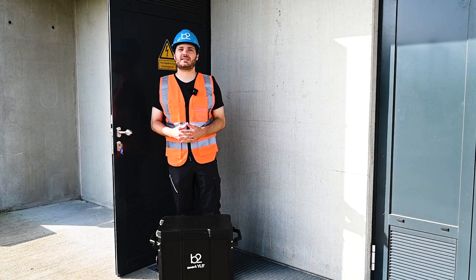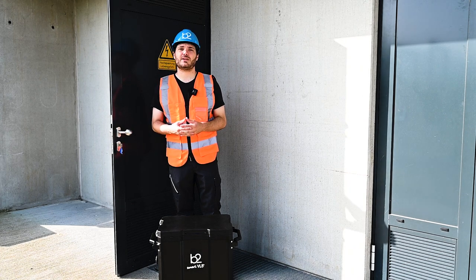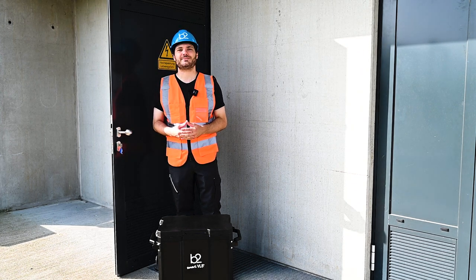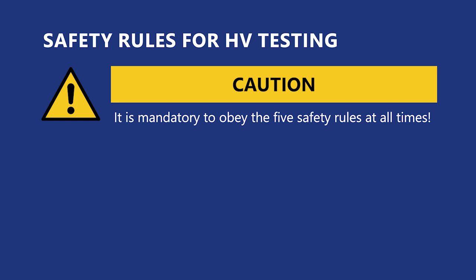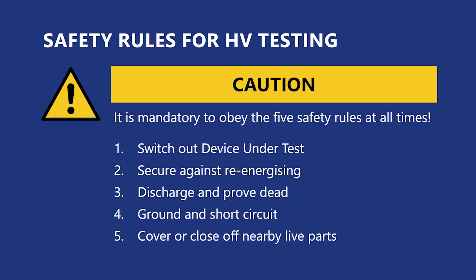Before you start with the setup, make sure that you comply with the safety regulations in force in your country and that you have familiarized yourself with the software, operating instructions of the devices, and the B2 safety guide. And always observe the following points: switch off the device under test, secure against re-energizing, discharge and prove dead, ground and short circuit, and cover and close off nearby live parts.